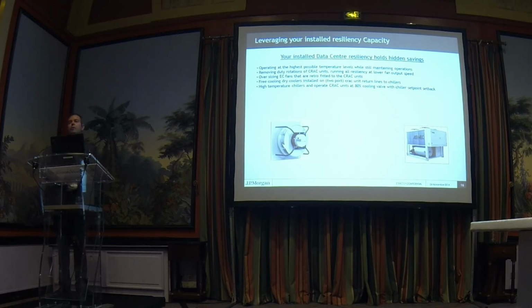Once you put the set point back up, the chiller backs off. Every degree you back your chiller off up a degree, you save about 4%, depending on the chiller. So when you're looking at a 30-degree day outside, and I have to supply water at 20 degrees, and we're doing 10K of cooling, the chiller load comes in where the outside air temperature versus the output temperature of the chilled water matters. The bigger the temperature outside, with the water temperature constant, the harder the compressor has to work. But if you put the temperature up on the supply water to the data center, the chiller actually has less work to do.